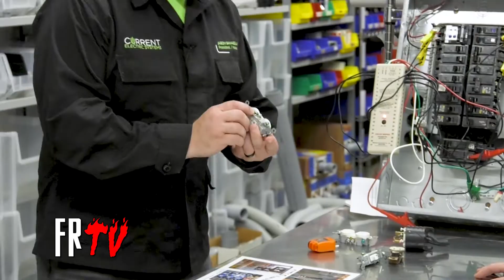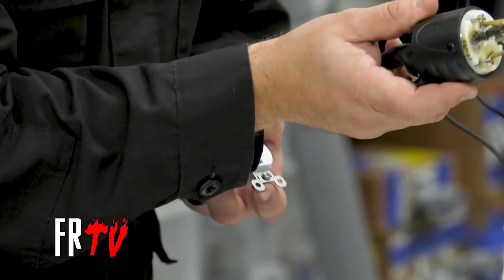As you can see in this example, one we saved from a recent service call, if there's deformation on the face of the receptacle, or you start seeing burning marks, or your plug looks like this, it's time. Sometimes you'll see a discoloration, or black soot marks. Absent that, another thing you're looking for is when you plug in, it should grip firmly.